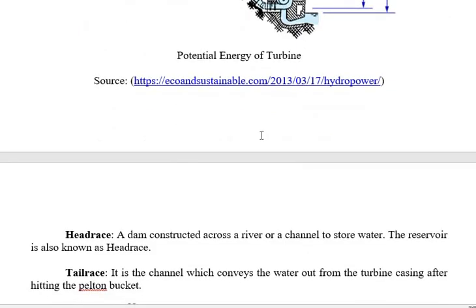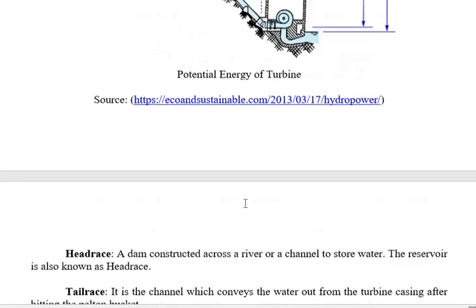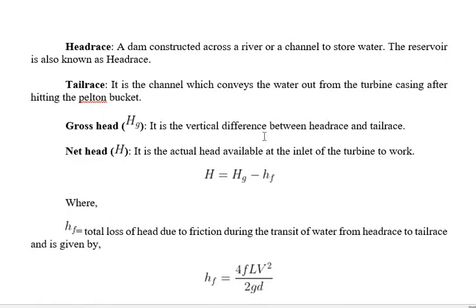The head race is the reservoir or dam. The tail race is the channel connected after the water exits from the turbine casing after hitting the Pelton buckets. The gross head is the vertical difference between the head race and the tail race. The net head is the actual head available at the inlet of the turbine, which accounts for the loss of head due to friction during the transition of water from head race to tail race.